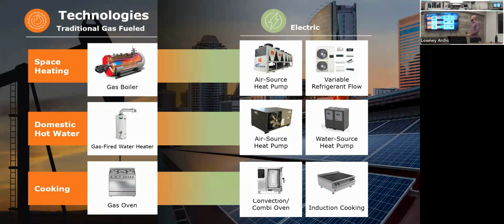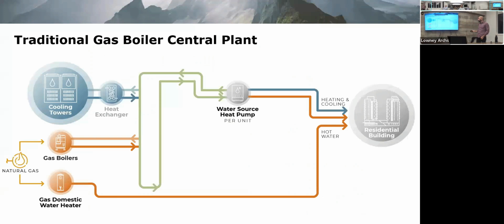And in some cases, you can also use water source heat pumps. Let's say you have a ground heat exchange loop, so you can do water to water heat pumps or air. Or if you have a district central plant, you can tie into that and do some heat recovery with this equipment as well. And for cooking, we have induction cooking appliances or convection combination ovens that we are seeing, and they're becoming more and more common.